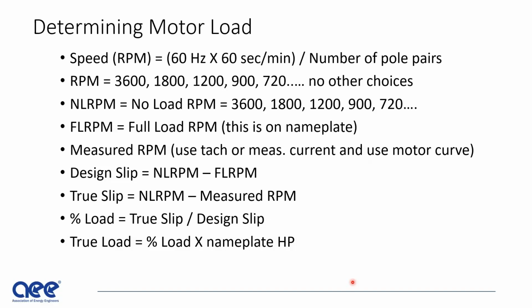Determining motor load. First, we look at the speed, which is the 60 hertz times the 60 seconds per minute divided by the number of poles. That's your RPM. The synchronous RPM is naturally going to be 3,600 or 1,800 or 1,200, because of the number of poles. There's no other choices but just those numbers. The no load RPM is pretty much equal to the synchronous RPM, and the full load RPM comes off the nameplate of the motor. The measured RPM needs to come from the current curve for the motor, or what we normally do is we put a tachometer on the shaft and get a direct measurement off the shaft of what the measured RPM is.